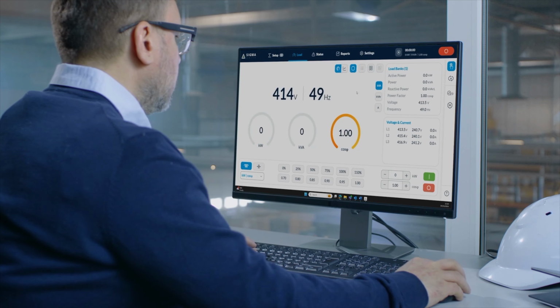As the size of data centers grow, we need to be able to scale when we test the design of them. With the networkability and scalability of the liquid-cooled load banks, we can put nearly 100 megawatts of load in one room and control it from a keystroke. That enables us to test larger and larger data halls for heat load and more equipment as we deliver larger packages of data center capacity.